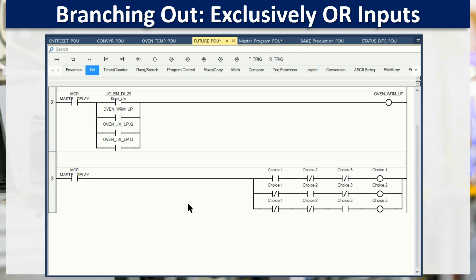And choice 1 says I'm making white bread, and this is how much white flour I need, this is how much sugar I need, this is how much milk I need, so many eggs to do a batch run of white bread. And choice 2 could be rye bread, and choice 3 might be pumpernickel. I can have an endless amount as long as I keep adding these not conditions. It prevents somebody from accidentally pressing it and starting it and having a half white and half pumpernickel or some confusing state. So this is called using a branch for exclusivity. It's another way of doing interlocking to prevent someone from making an accidental mistake on a selection.